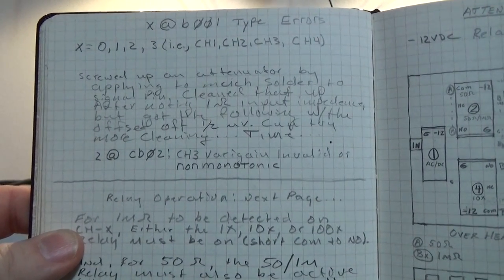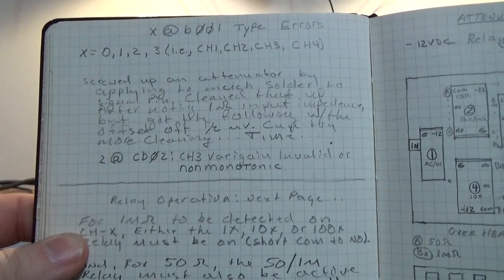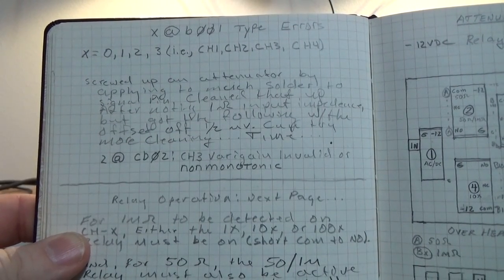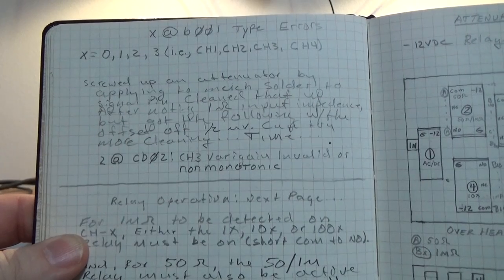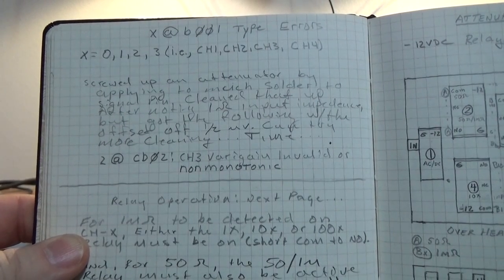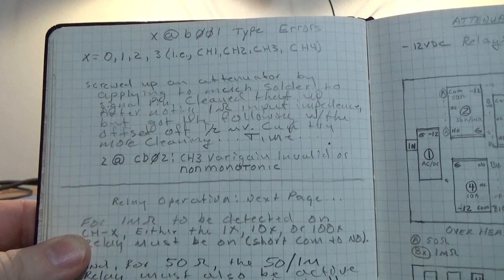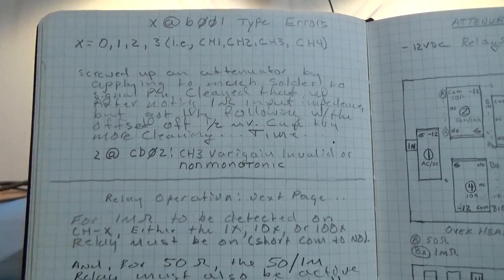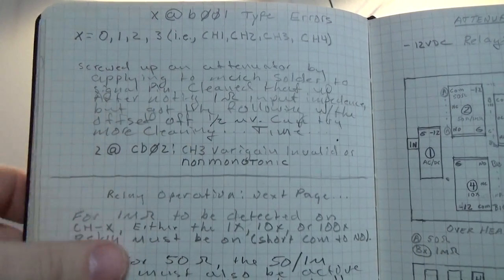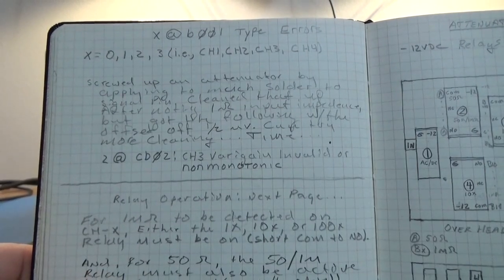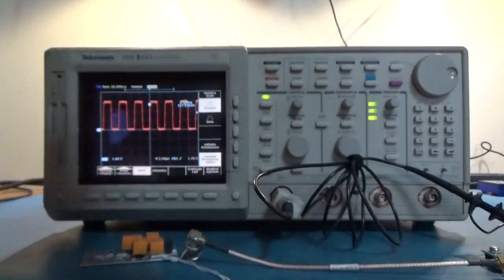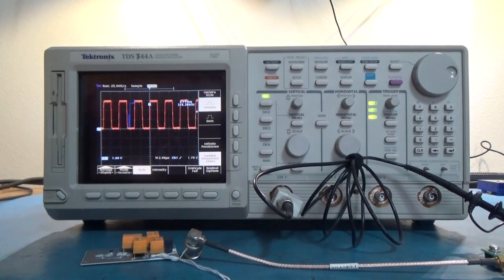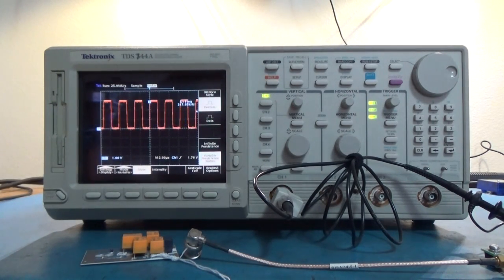So, at the very top on the left here, I'm telling you that if you get an error log thing that says, X failed at B001 type errors. The X is zero is channel one, one is channel two and three and so forth. And that can save you hours in trying to fix this thing.